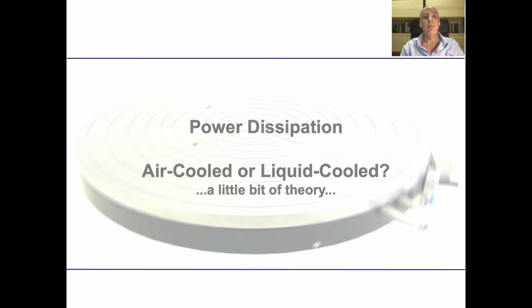Basically, heat or power dissipation means to transfer a thermal load away from the substrate, the wafer, or the device under testing. If the thermal load is larger than the heat dissipation capabilities of the thermal system, the chuck temperature will start to increase and cannot be controlled anymore. The rule of thumb is that the cooling capacity of the thermal system must be larger than the thermal load.